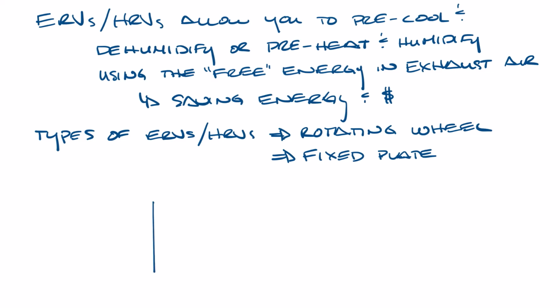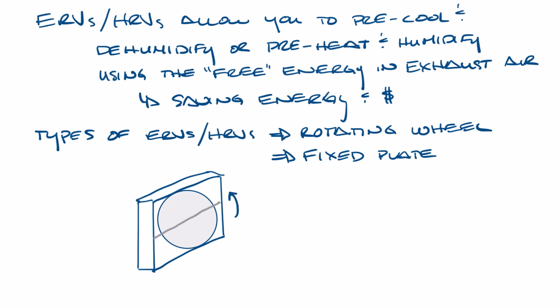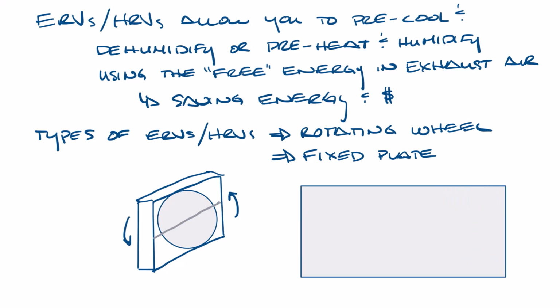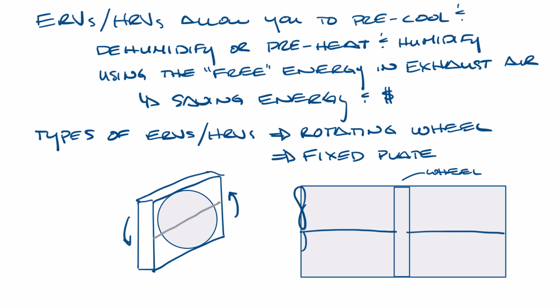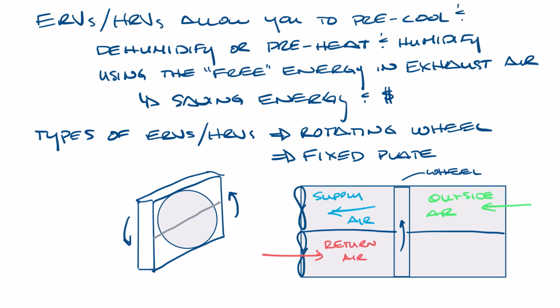So I'm going to draw the wheel in the frame first. So you have a wheel in a frame and it's separated like this. So it'll rotate through two separate sections in the ERV unit. Now if we put it in a cabinet like this, and then the wheel is here in the middle, we have fans over here to move the air in and out of the ERV. The outside air comes in here, goes through the wheel, and is blown out of the unit to become supply air over here. And we'll get to the details of this in a minute. The return air is pulled into this section and would pass through the lower half of the rotating wheel and then be exhausted out of the unit.